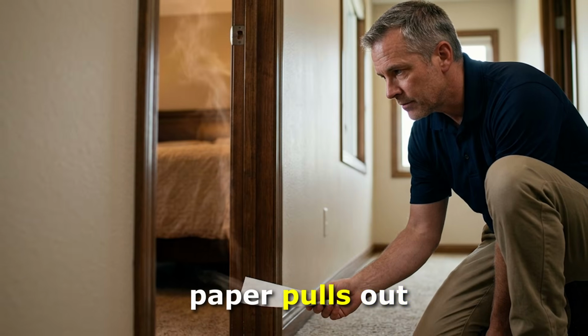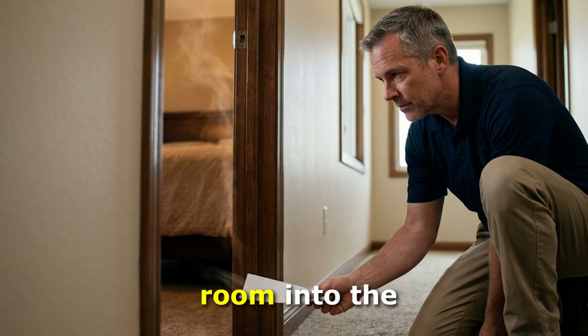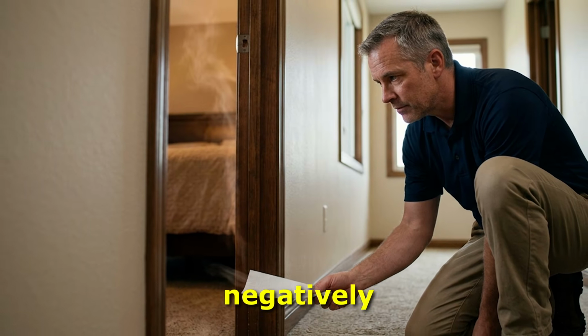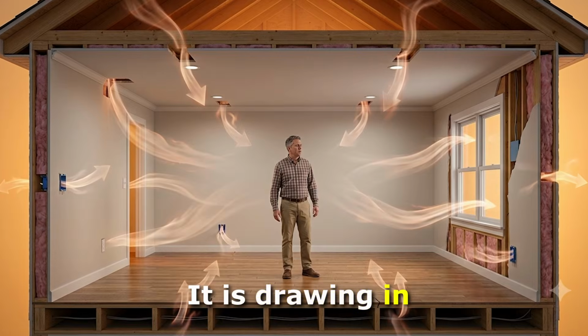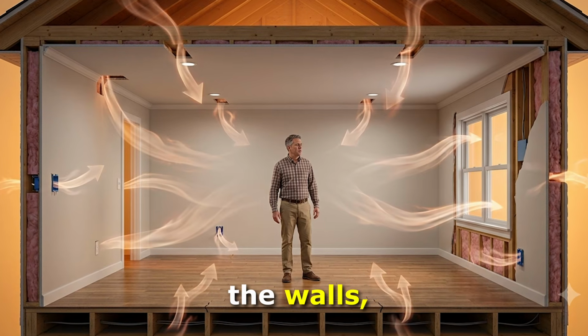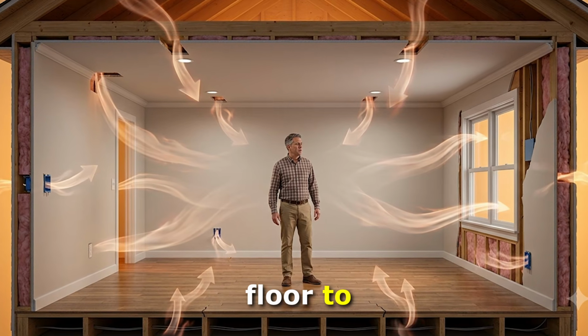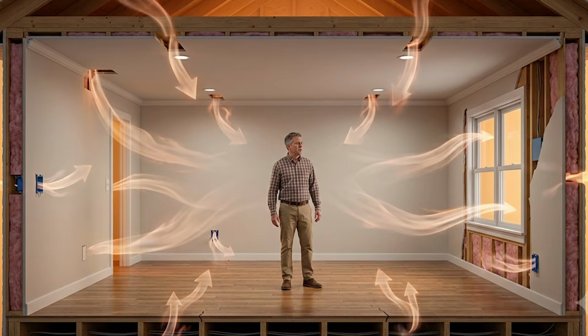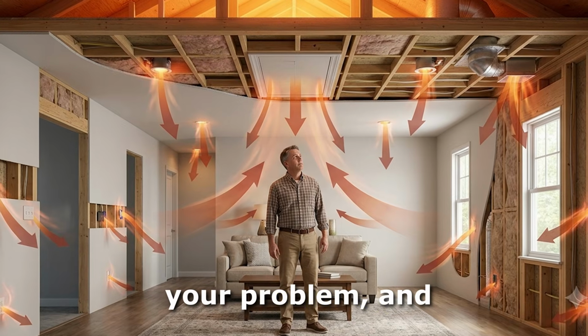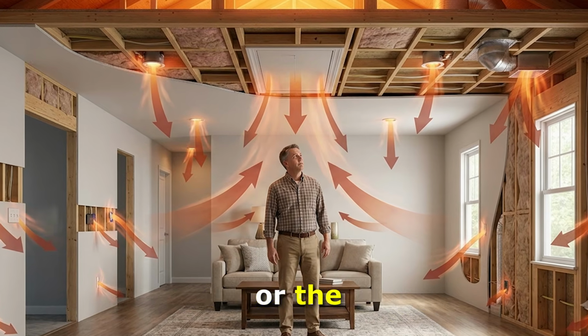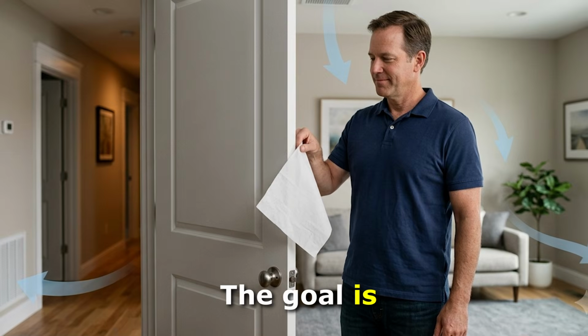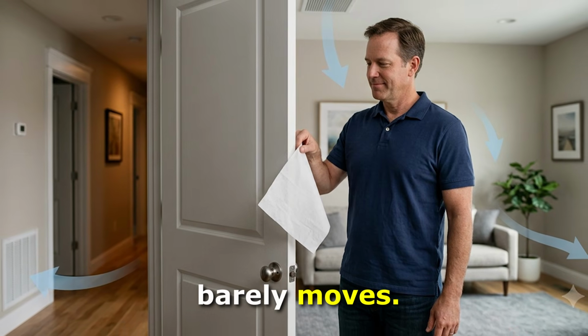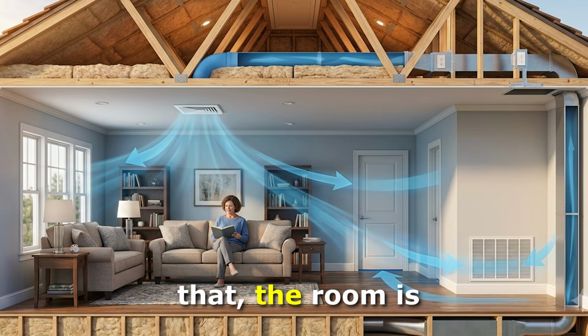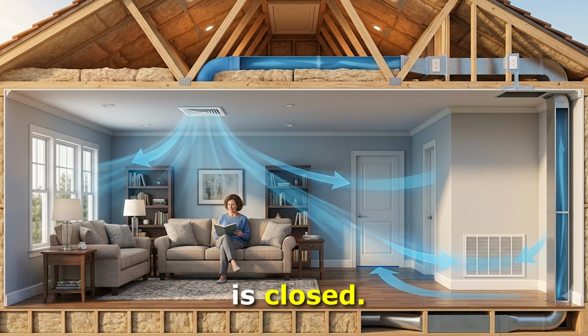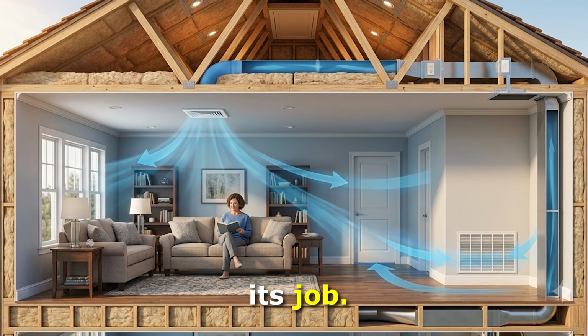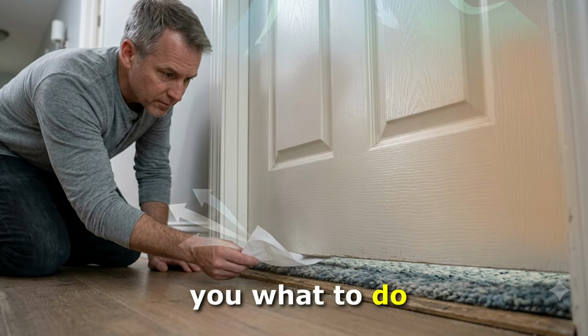If the tissue paper pulls out of the room, if it moves from the room into the hallway, the room is negatively pressurized. It is drawing in outside air through gaps in the walls, ceiling, and floor to compensate for the pressure imbalance. Those gaps are your problem, and they are in the ceiling above you or the walls around you. The goal is neutral pressure. The tissue paper barely moves. When you achieve that, the room is balanced, the loop is closed, the system can do its job. Now let me show you what to do about each type.